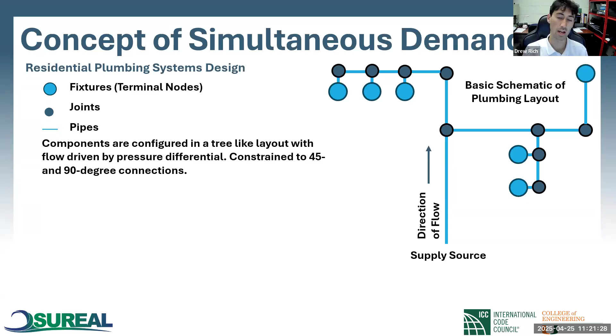Now, understanding this, each pipe upstream, or opposite the direction of flow, right? So if we're looking at a terminal node here, every pipe that's leading up to that has to be able to supply enough water and pressure for all of the fixtures downstream of it, right? So again, we have to look at designing with that in mind.